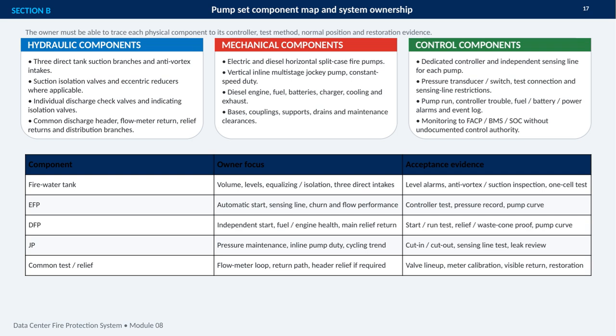Control ownership includes a dedicated controller and sensing line for each pump, pressure sensing devices, test connections, alarms, and event logs. Monitoring can reach the fire alarm panel, building management system, or security operations center, but without undocumented control authority. Acceptance evidence must match the component. That includes tank level and suction inspections, pump controller and curve records, diesel relief and engine tests, jockey pump cycling and leak reviews, and documented valve lineup, meter calibration, visible return flow, and restoration for common testing.